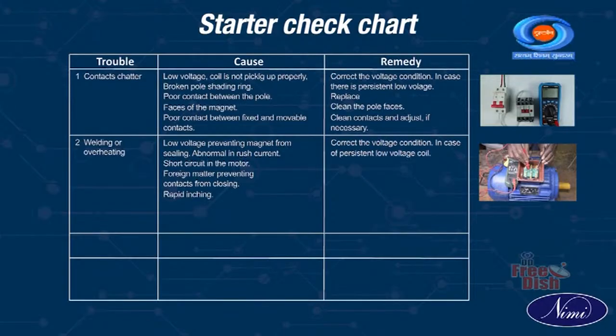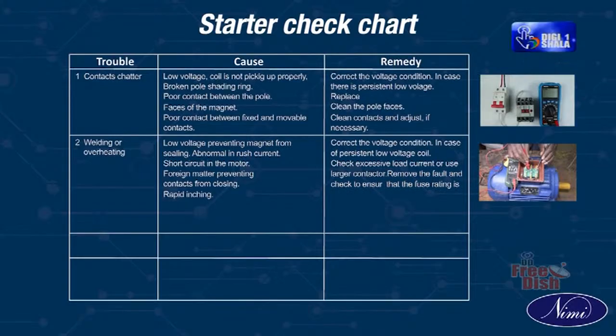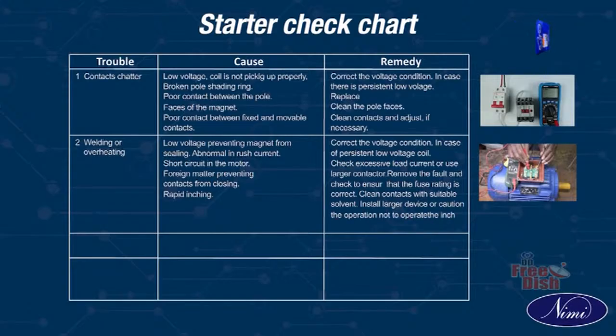Correct the voltage condition. In case of persistent low voltage, check the coil, check excessive load current or use a larger contactor. Remove the fault and check to ensure that the fuse rating is correct. Clean contacts with suitable solvent. Install larger device or caution the operator not to operate the inch button too quickly.